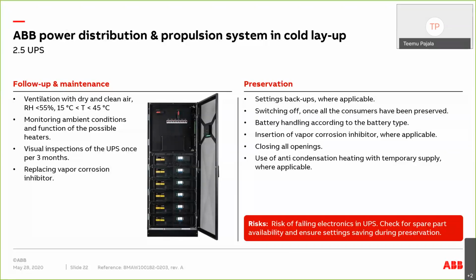And battery is a special thing in the UPS, and those must be handled according to the battery type. There is a lot of different types of batteries used in UPS, so it's not possible to say one way of handling the batteries. So always please check what type of battery, how to handle it. Some need to be switched off or disconnected, some need to remain connected, some might need to have a charging available to keep the energy inside, and so on. And again, use the corrosion inhibitors where applicable and close all the openings.